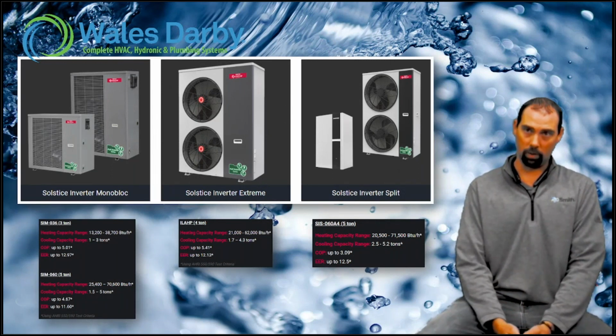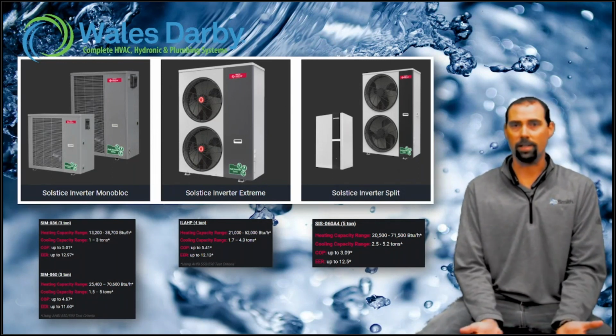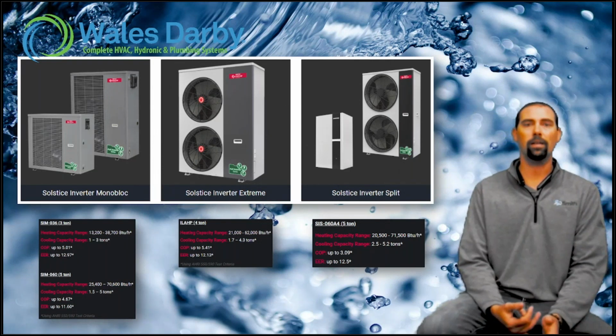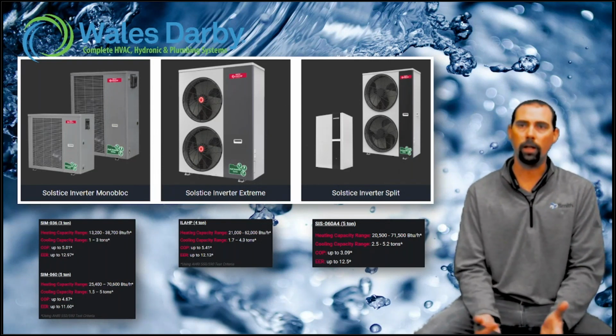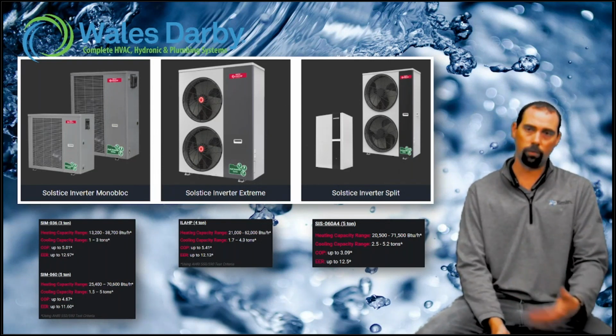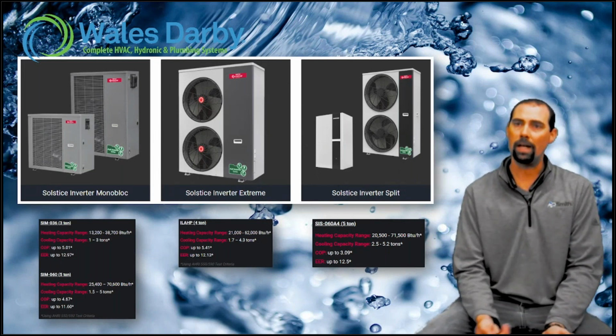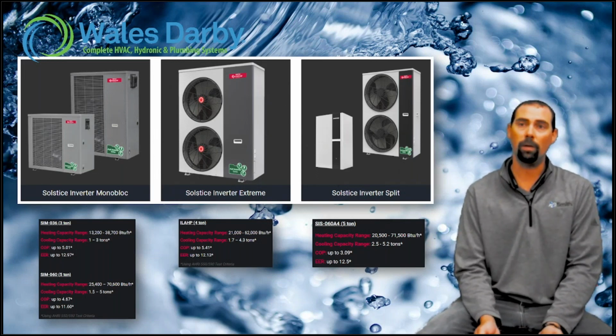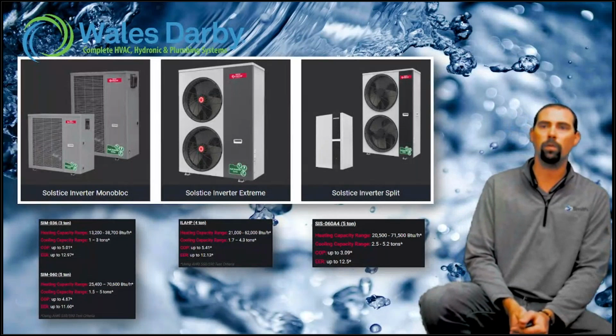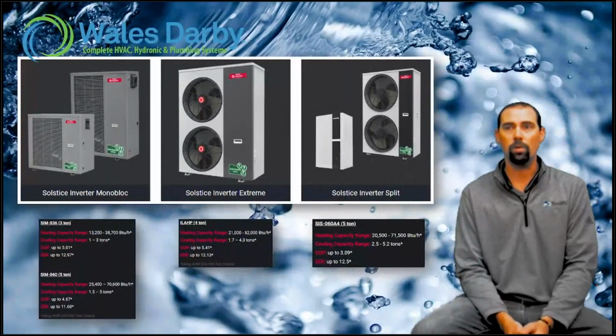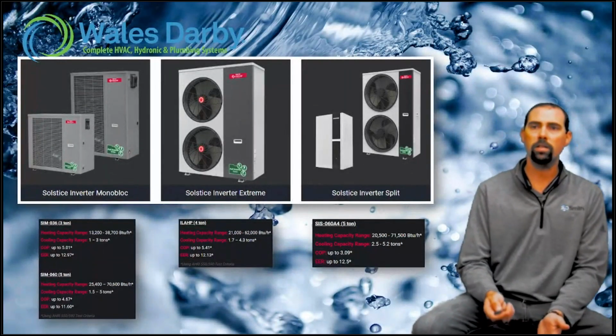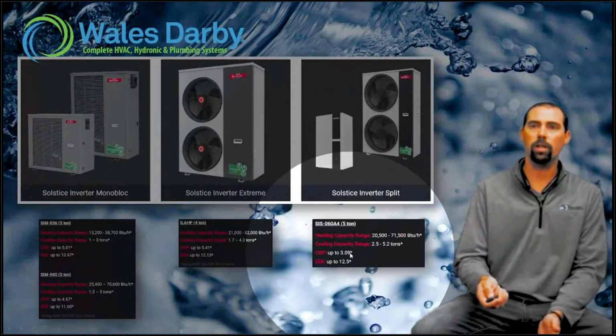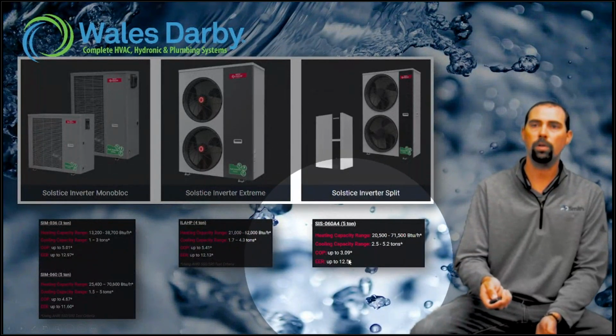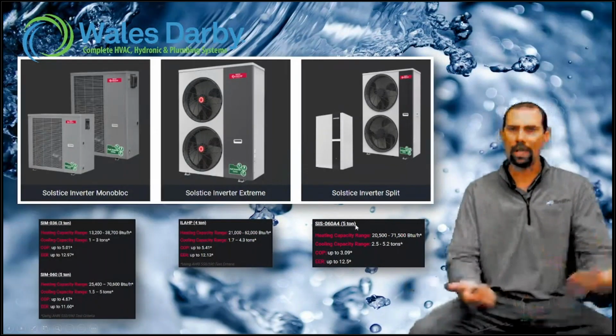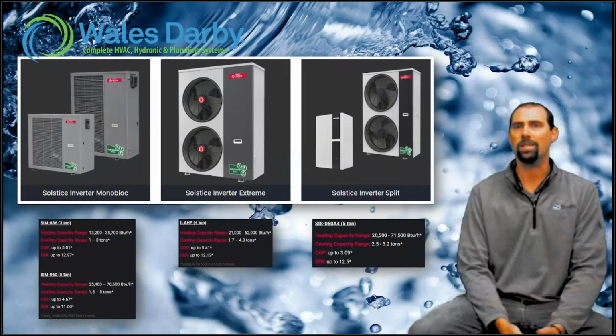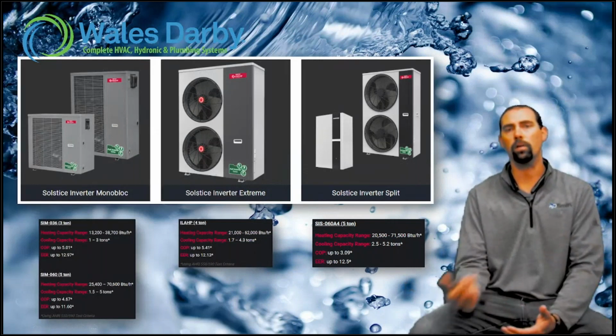Your refrigerant lines will connect the two. This comes as a system, so you will get the line set, the control cable, everything you need to hook up the two of those together, and then go from there to your buffer tank. So even that system, that's a 5-ton system, up to 71,000 BTUs for heating, up to 5.2 tons of cooling. COPs down a little bit, closer to that 300% range we were talking about, right? 3.09.